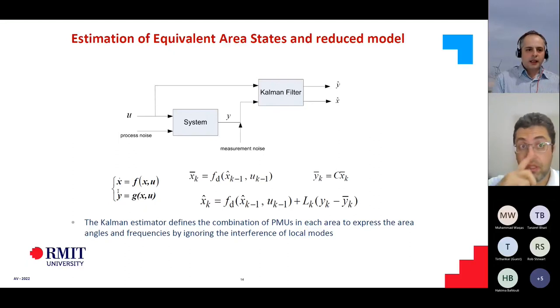Generally speaking, it totally depends on the frequency of the measurements we have. If we rely on PMUs, they usually have a higher sampling frequency, but the data is sent at a sampling rate of either 50 hertz or 100 hertz. So in the lowest case, we have around 20 milliseconds between each sample. For data transmission, I wouldn't expect more than 50 milliseconds or so in delay.